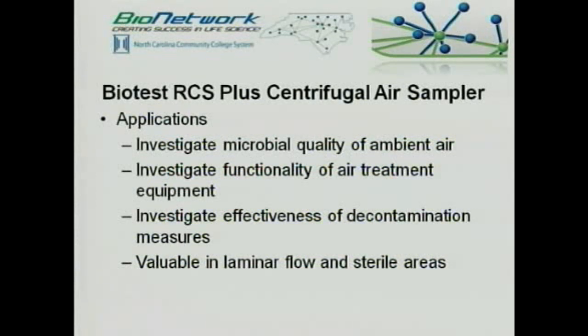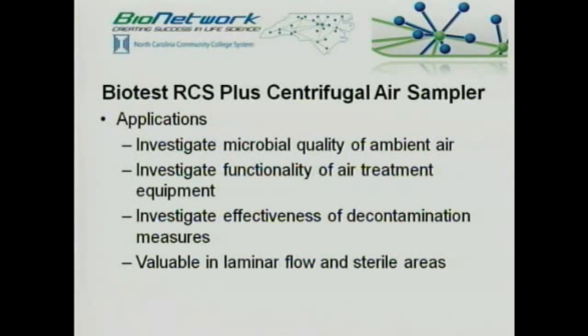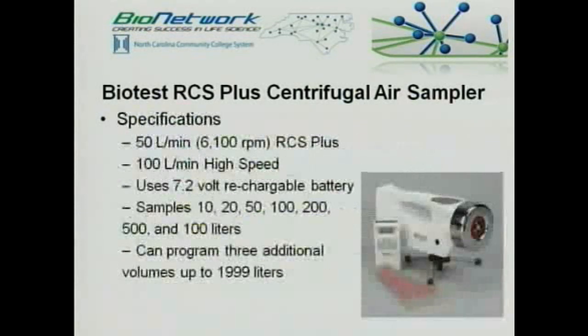Now let's look at a centrifugal air sampler. Centrifugal air samplers are used for sampling viable—living—contaminants within the air. This particular RCS Plus centrifugal air sampler has many applications: we can use it to investigate the microbial quality of air in our working environment, evaluate how effective our air treatment equipment and HVAC filtration are, determine how effective our decontamination procedures are, and evaluate air quality in laminar flow hoods, rooms, or any sterile area.